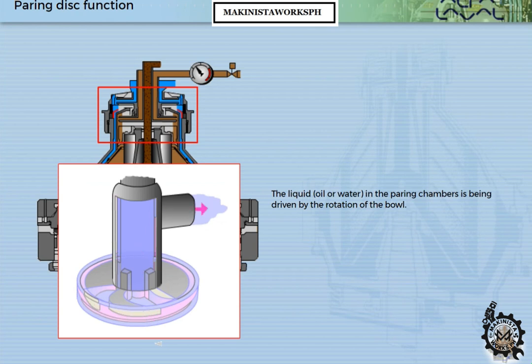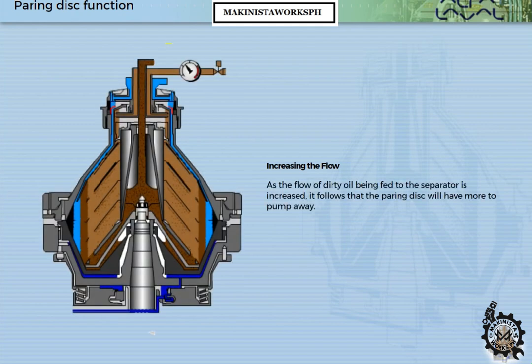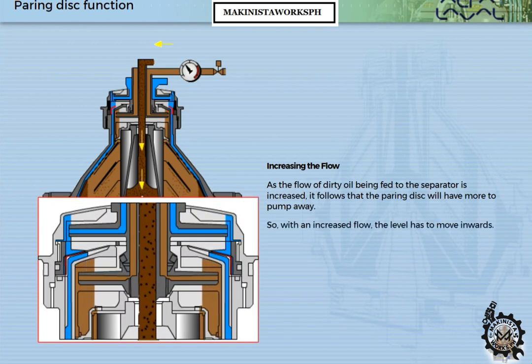The liquid — oil or water — in the paring chambers is being driven by the rotation of the bowl. As the flow of dirty oil being fed to the separator is increased, the paring disc will have more to pump away. So, with an increased flow, the level has to move inwards.